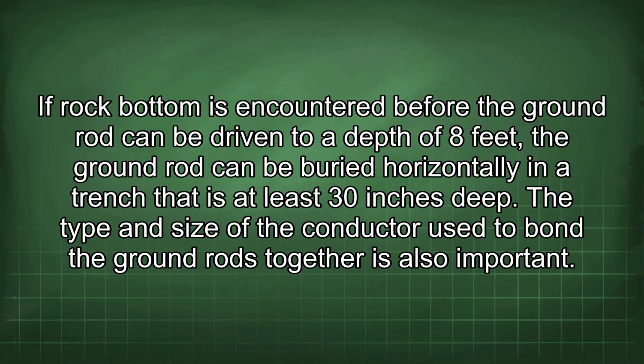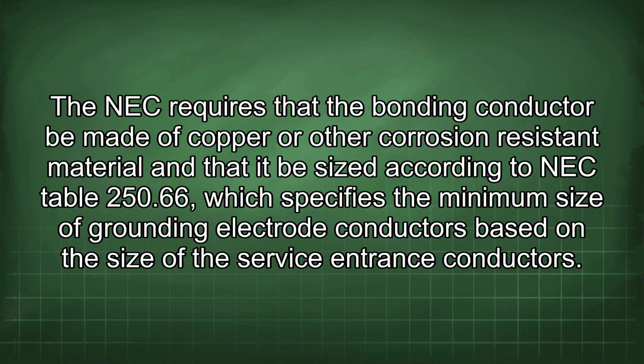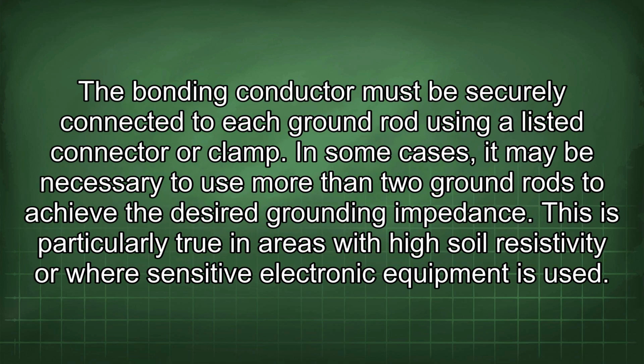The type and size of the conductor used to bond the ground rods together is also important. The NEC requires that the bonding conductor be made of copper or other corrosion-resistant material and that it be sized according to NEC Table 250.66, which specifies the minimum size of grounding electrode conductors based on the size of the service entrance conductors. The bonding conductor must be securely connected to each ground rod using a listed connector or clamp.